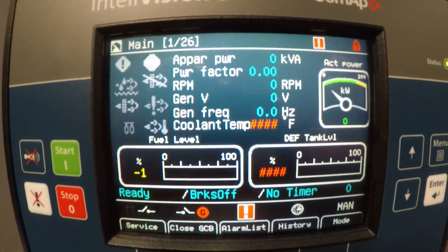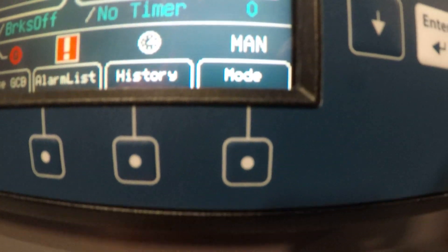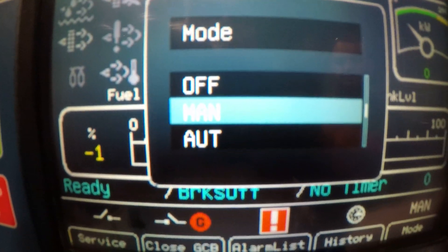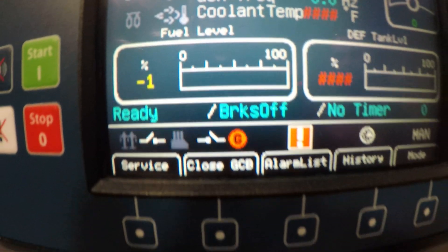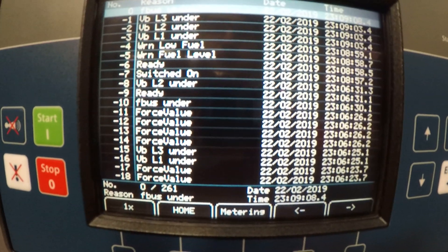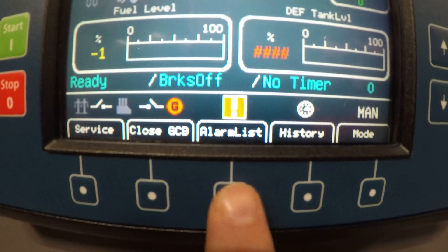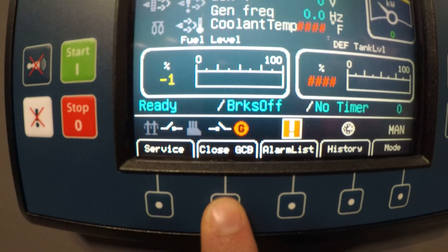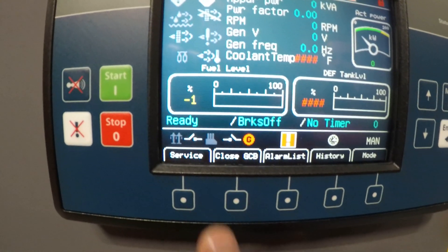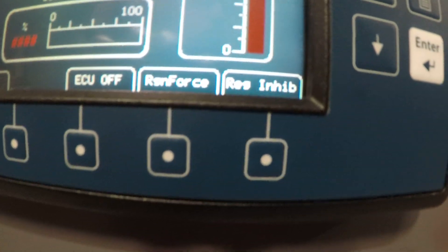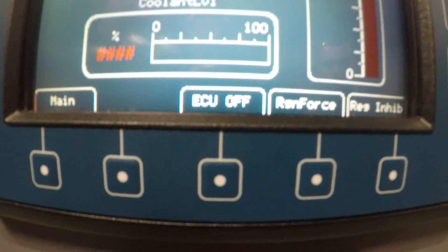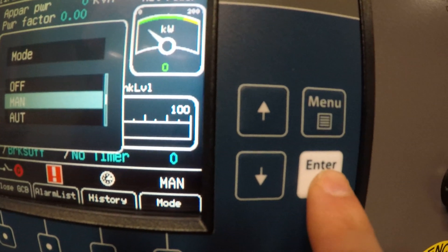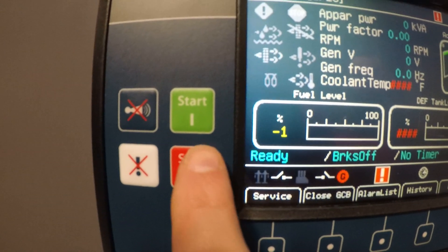Main page starting sequence to start the genset. You got an option down here on this tab called mode. You got the off position, the manual start control, and auto start control. To the right of that you got the history page, your alarms page which shows low fuel, the generator circuit breaker open and close push button for your motorized breaker, and a service tab for force regen, regen inhibit, or ECU override power on. To select manual start, hit the mode button, make sure you're in manual, select enter, mode will change to manual, and from here you push your green start button.